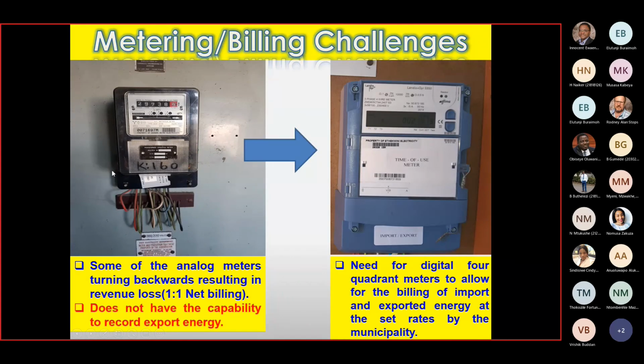The other challenge is that we've got a lot of old disk meters, and when the customer is feeding back into the network, especially on the residential and small business side, the meters turn backwards. This essentially means one-to-one net billing, which is a revenue loss. Going forward we need four-quadrant digital meters that can be programmed with different registers, but these are more costly meters, and rolling them out is significant considering the municipality has over 750,000 customers.